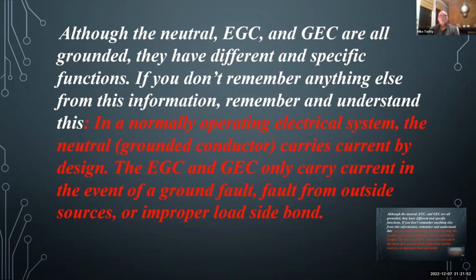Okay, although the neutral, the equipment grounding conductor and grounding electrode conductor are all grounded, they have different and specific functions. If you don't remember anything else from what we're talking about tonight, remember and understand this. In a normally operating electrical system, the neutral carries current by design. The equipment grounding conductor and the grounding electrode conductor only carry current in the event of a ground fault or a fault from outside sources. Lightning can put current on it, or improper load side bond. That can put current on those conductors that are not intended to carry current except in a fault. But a neutral, it carries it by design.